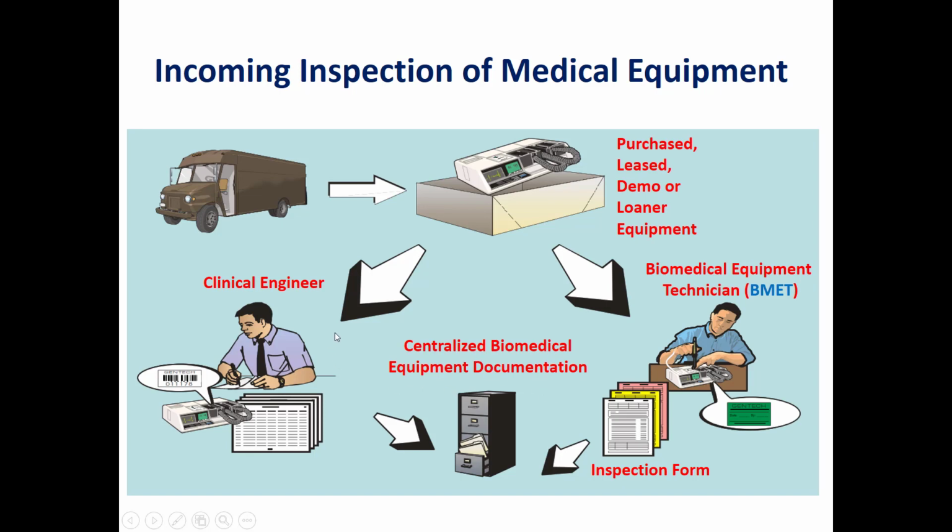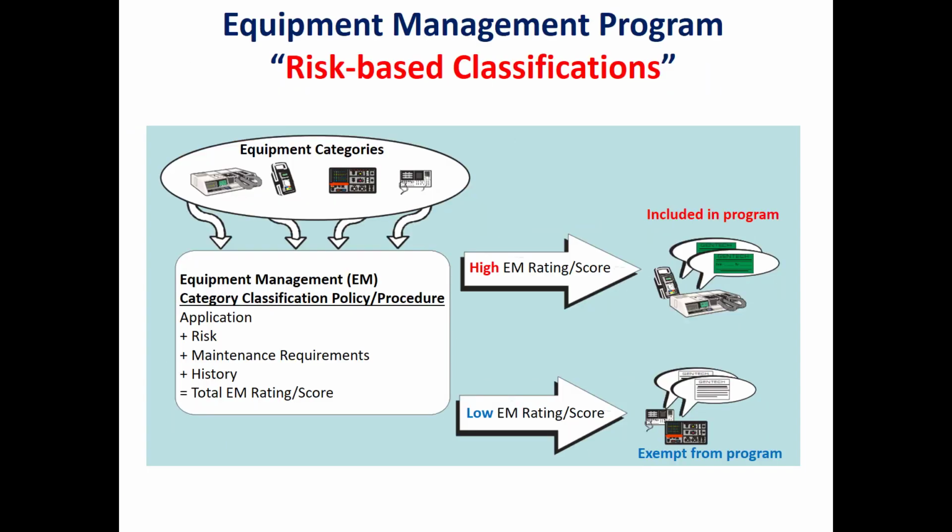And the clinical engineer will, first of all, make an inventory number for this new medical device and enter it into the inventory of this department or of the hospital, the medical equipment inventory with the related data. Each of this work was paper-based in the previous system, whereas now it is computerized or a soft copy.